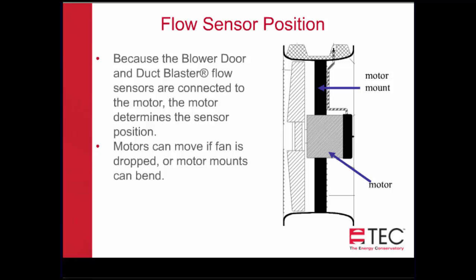Flow sensor position is also important, and this is what affects calibration. So what we want to do is measure the distance between the flow sensor and a reference point, and the reference point is the outside perimeter of the fan housing. Now, the fan motor is able to move in and out of the fan housing. We try to keep it locked down as best as we can, but occasionally, if the fan is dropped either on its face or on its back, it might have a chance of moving the position of the motor forward or backward. So we want to make sure that that's good.